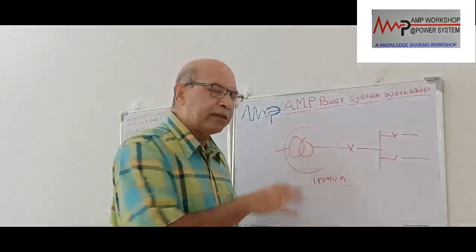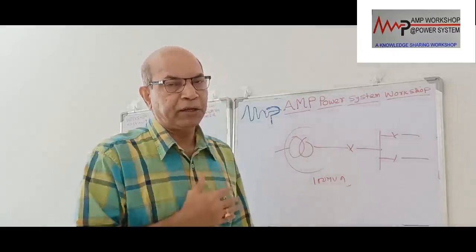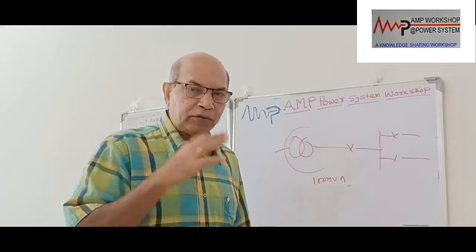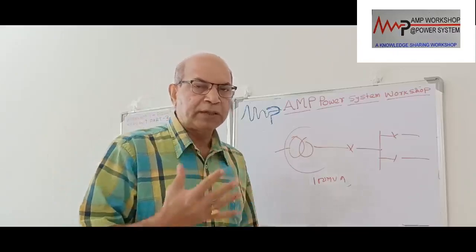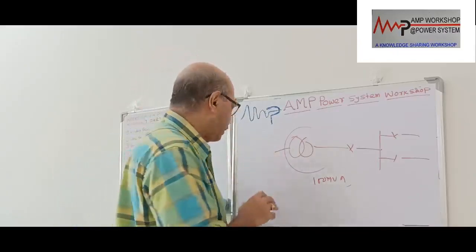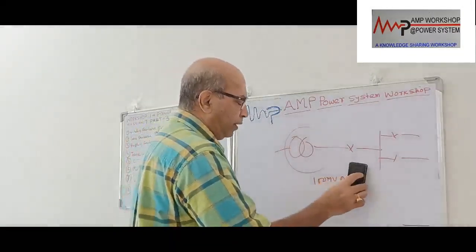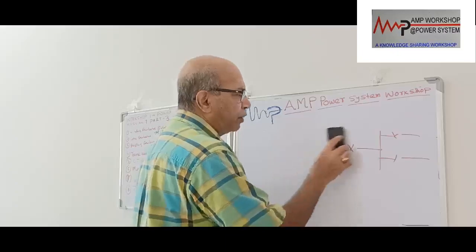In that case, we have to replace the transformer. That is also a long time to manufacture this type of transformer and bring it into place. After the installation, testing and commissioning, it will also take more than 1 year. So that's why we need to protect the transformer as far as practicable, so that such a major failure can be prevented. That is the intention of the transformer protection.